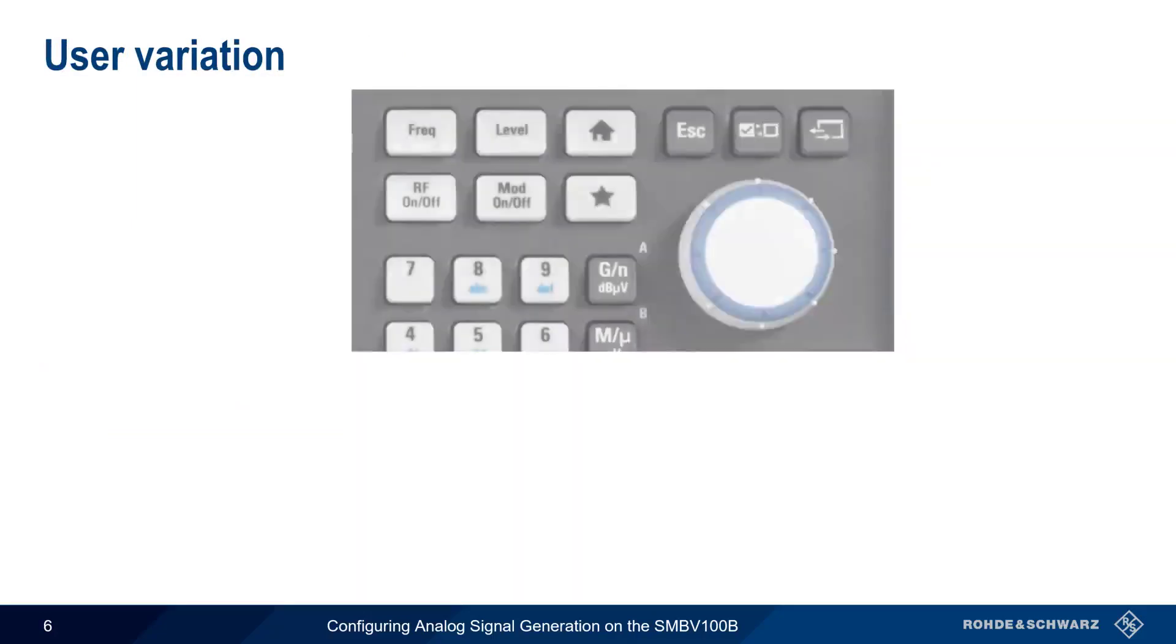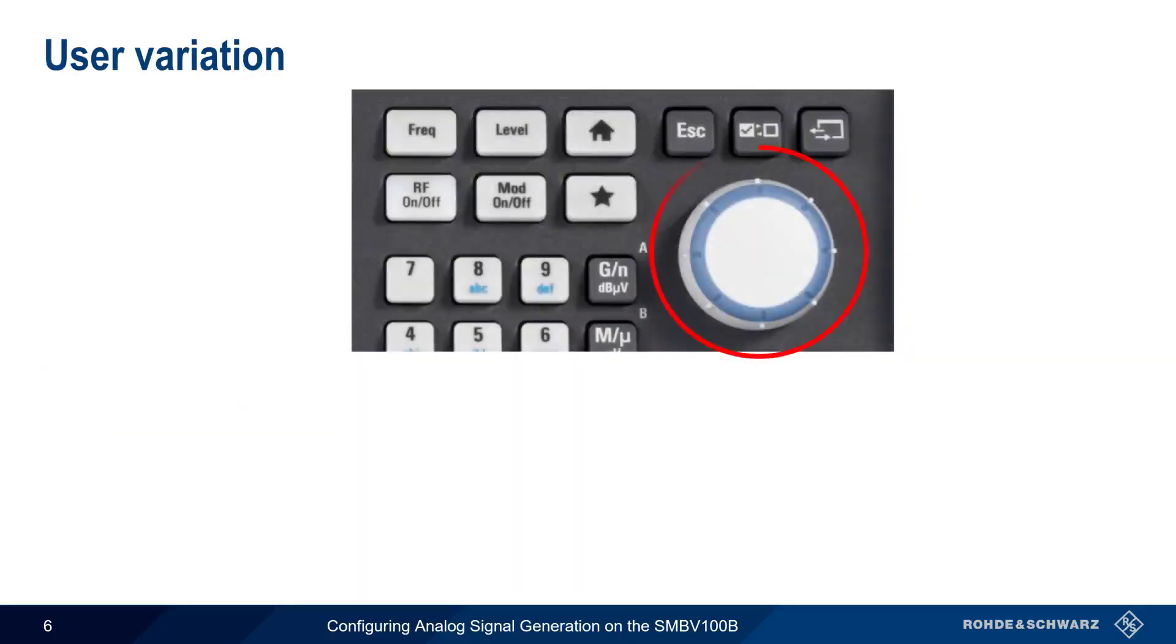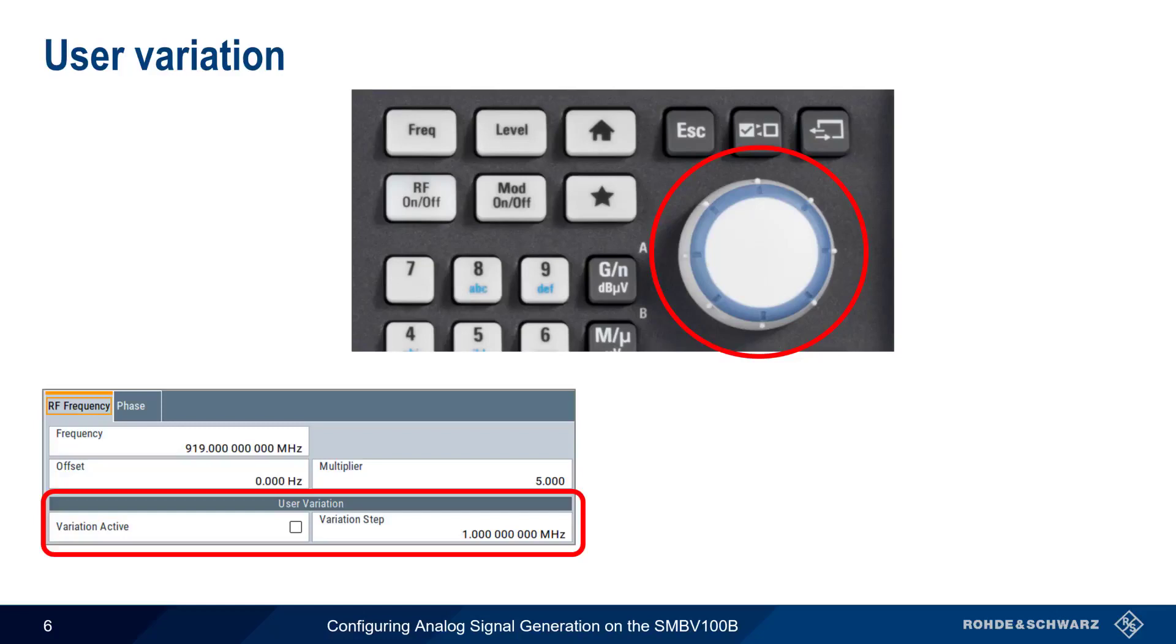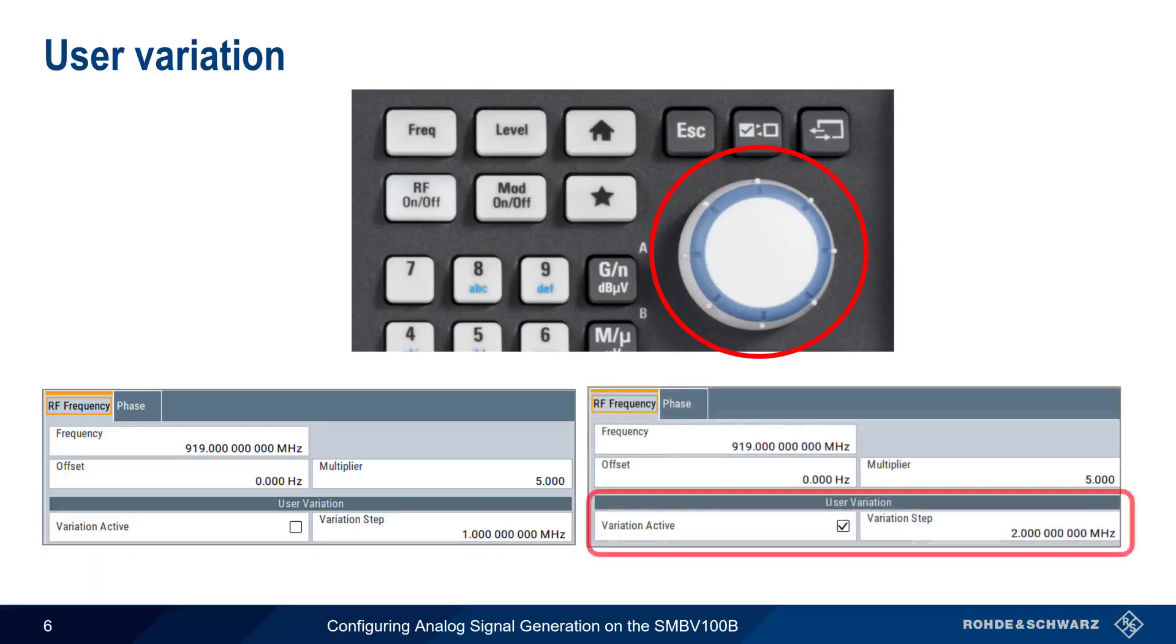In different places within the SMBV100B, you may come across a setting called User Variation, which simply controls the step size when using the rotary knob. For example, in Frequency mode, the default step is 1 MHz when using the rotary knob. By enabling User Variation, we can define how much each click of the knob changes the frequency. For example, if we enable User Variation and set the step to 2 MHz, each click of the rotary knob will change the frequency by 2 MHz. You'll also see User Variation used for other parameters, such as Level.